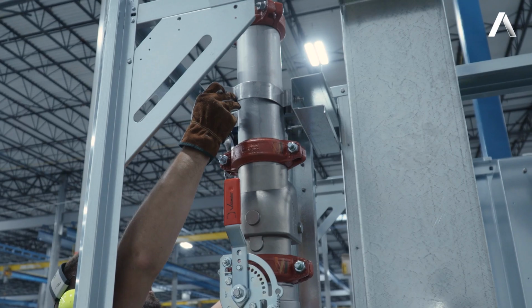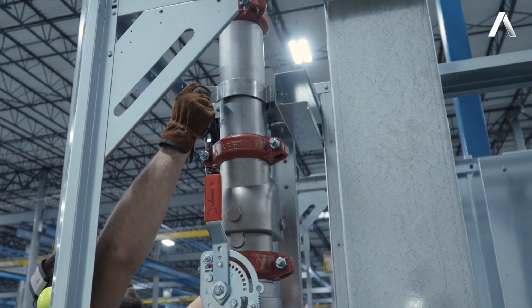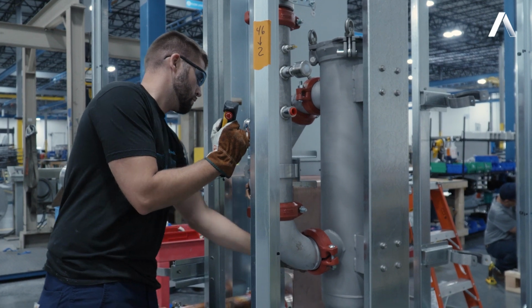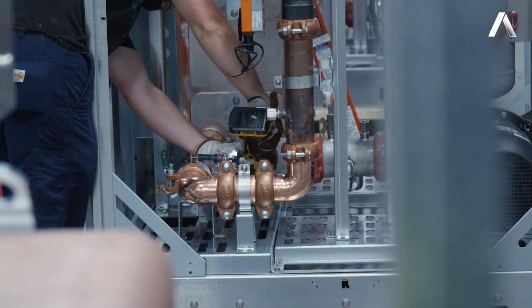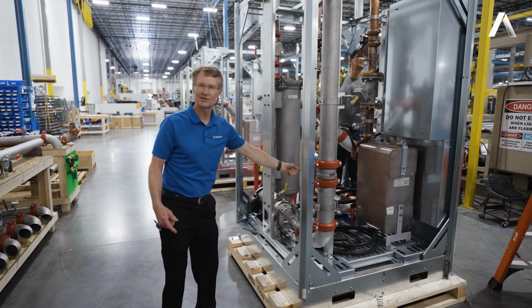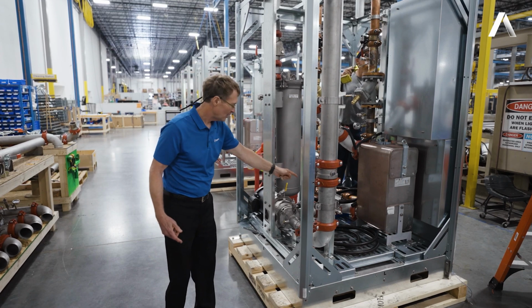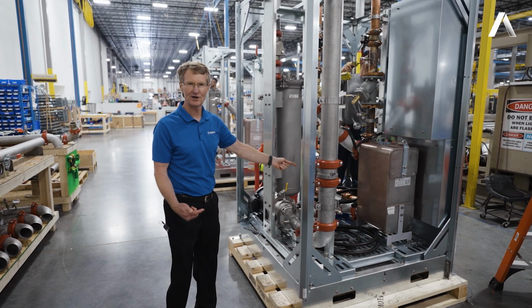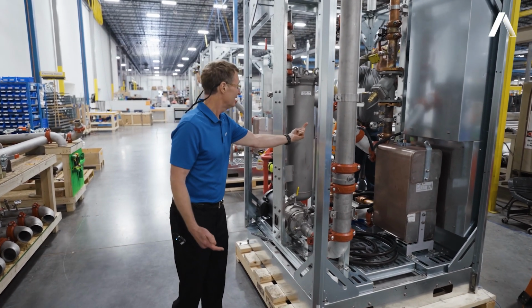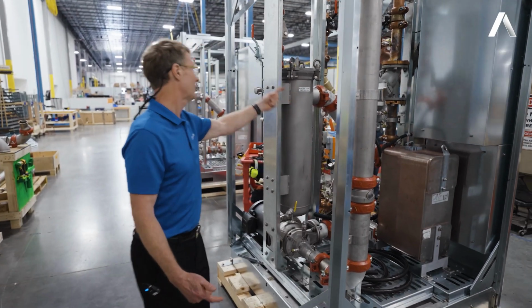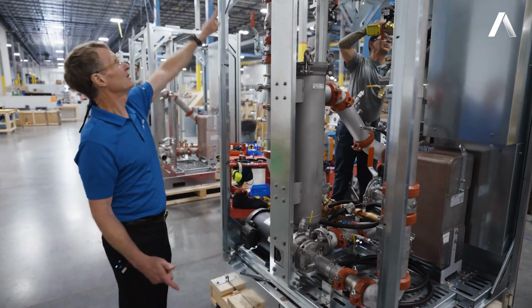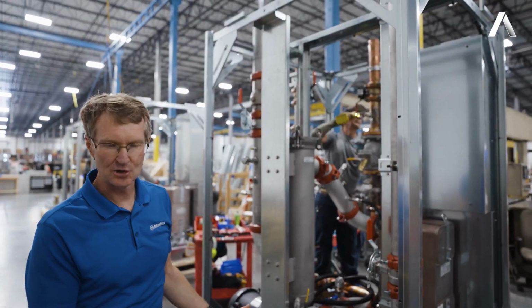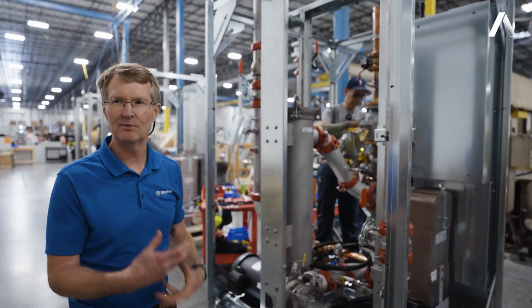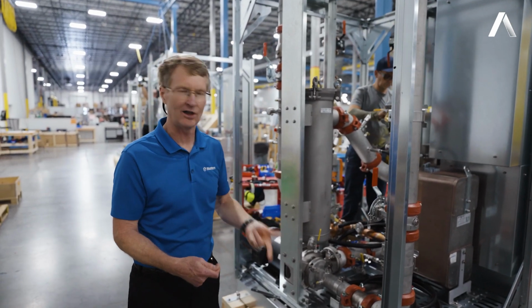Continuing down, we've now added our 25 micron filter for the technology fluid. From the pump, discharge goes into the heat exchanger where that warm fluid from the servers is cooled down. It then goes into the filter, comes out of the filter, and goes back to the servers to reabsorb the heat and begin the cycle all over again.